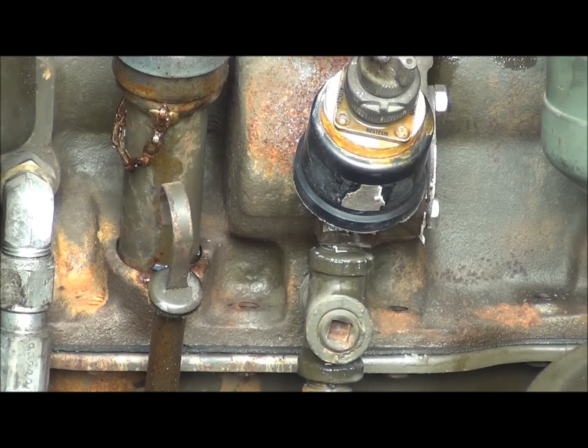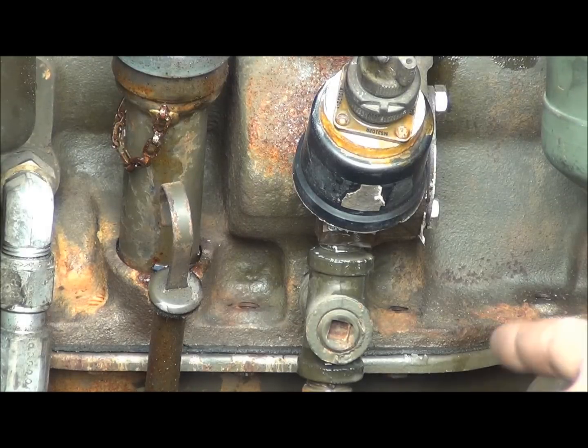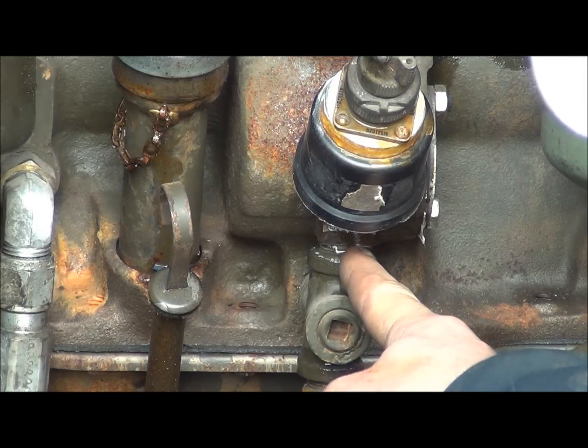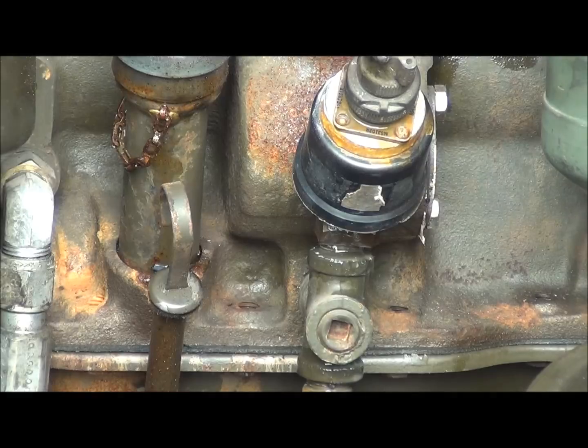Alright, during the last several runs I've been going around the generator and just taking a look at things each time I shut it down, just continuing to check for leaks and any other obvious problems. And I noticed it hasn't started to drip yet, but I do notice a little bit of an oil sheen showing up right here. This is where I installed the oil pressure switch in the last video, and it looks like I probably just didn't get it tight enough. I did add thread sealant to it, but I didn't tighten it down with the wrench because I didn't want to mess up the threads or risk breaking the pressure switch. So I'll go ahead and get a wrench on it and tighten it down a little bit more, clean it up, and see if we've stopped that little leak.